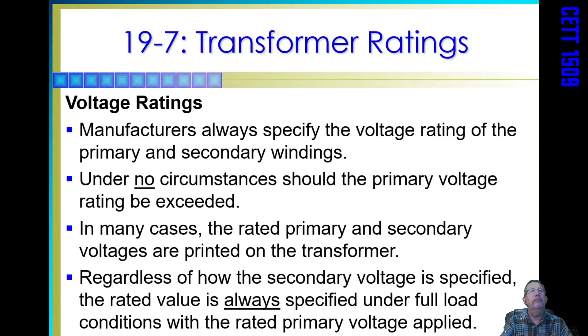So in many cases, the rated primary and secondary voltages are printed on the transformer, right? Regardless of how the secondary voltage is specified, the rated value is always specified under full load. In other words, it's the maximum that you'll get when the rated primary voltage is applied. So those are the maximum amounts according to the ratings. Current ratings: manufacturers usually specify current ratings only for the secondary windings. If the secondary current is not exceeded, there's no possible way the primary current can be exceeded, right? Because remember, it's that ratio. So they say you can only have this much current on the output, and that's what's used in calculations.